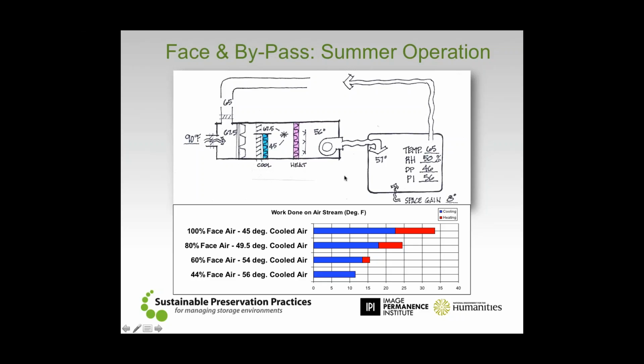And if I continue recirculating air at those conditions, then I'm eventually going to achieve this dew point of 45 degree, or this 46-degree dew point in space, because I'll catch some of that moisture every time it comes back around in the system. So that's a high-level experimentation, but it's meant just as an example: if you have this type of air path arrangement within the mechanical system through a face and bypass arrangement, don't just take it for granted that whatever those dampers are set at is exactly the right blend or exactly the right quantity of air moving around.